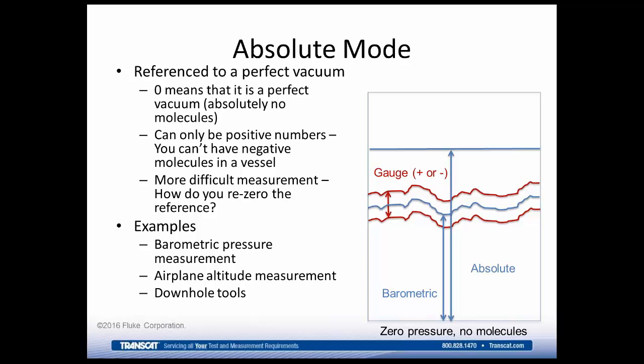Absolute mode, now you're referenced to a perfect vacuum. And we see that in a diagram to our left, or to the right, excuse me. In this diagram, we show that there's this blue line that's moving all around. That is our barometric pressure, or atmospheric pressure. Gauge is simply the difference between that blue line and our test pressure. So that's represented by this red. And it can be a plus or a minus, plus being above pressure, above atmosphere, minus being below.